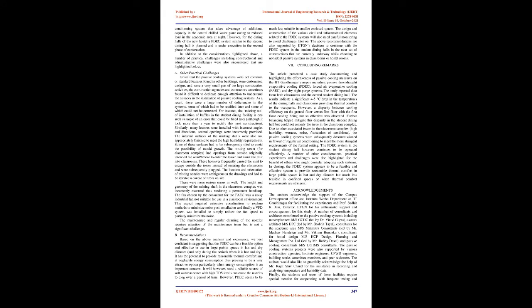4. Principle of operation. In both PDEC and FAEC systems, the misting system is close to the highest point within the downdraft tower. When the fine mist released from the misting nozzles comes in contact with dry, warm air, the mist evaporates, absorbing heat from the surrounding air to serve as the latent heat of evaporation, thereby resulting in a drop in dry bulb temperature of the air, while increasing the humidity of the air. This cooler air being heavier drops downwards in the tower, creating the passive downdraft.